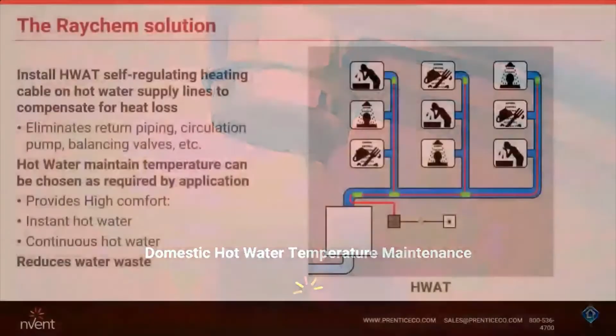In most applications, domestic hot water is done with a water heater and a pump, and you circulate the water around a building. Just know that we have a solution that, by using heat trace, provides a consistent and manageable temperature all the way to the end point without having to recirculate it. So we are eliminating all the return piping, all the circ pumps, the balancing, which is usually problematic when you get into high-rise building applications.